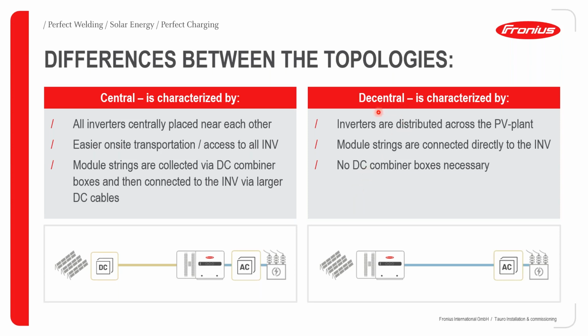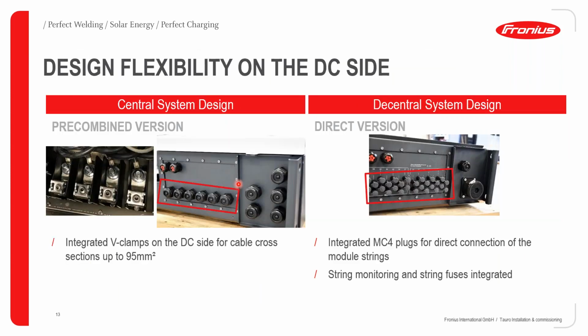Therefore, a decentral design has one cost-saving element, that the DC combiner boxes will not be required, but with a central design, DC combiner boxes will, in most cases, be required. So as I've mentioned, the Tauro will give us a lot of flexibility as far as design is concerned. And one of these flexibilities is the design on the DC side.